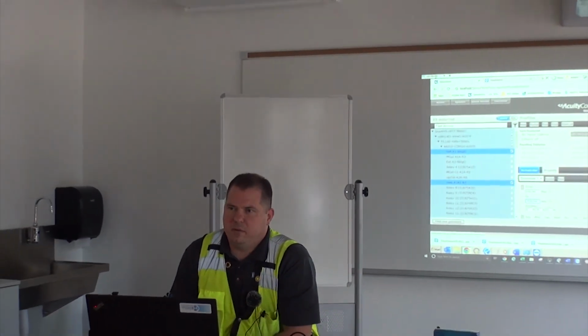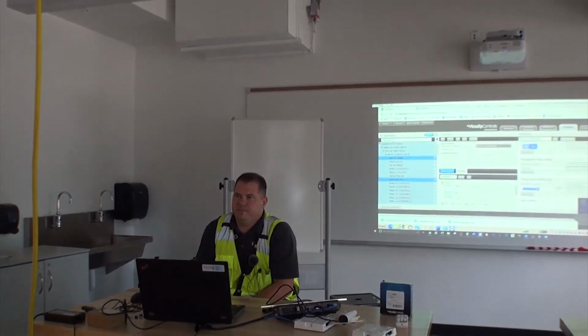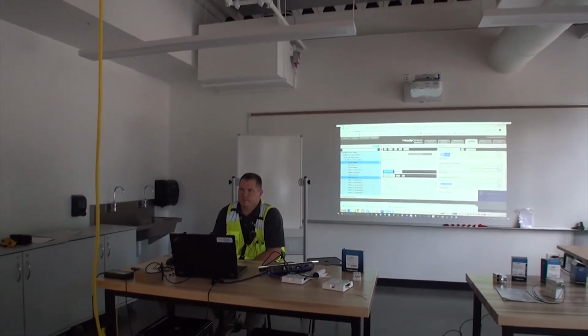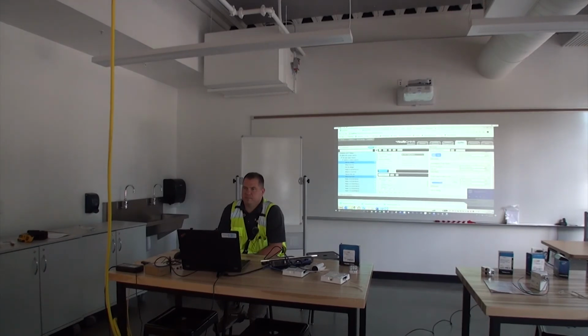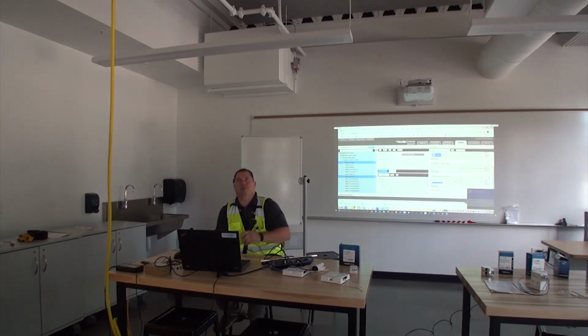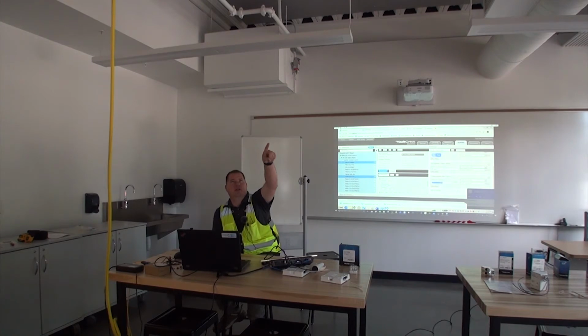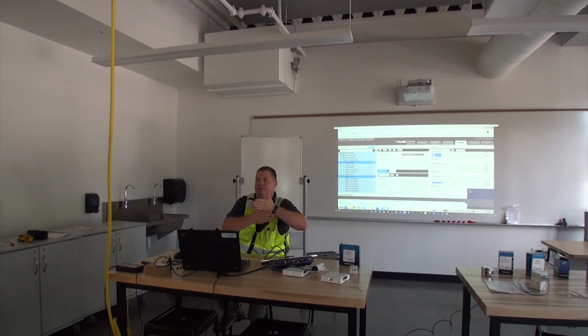As far as troubleshooting goes, I noticed it says to keep a 90-degree angle across power path lines and stuff when someone comes in to run power, since it's an inductive pump and not shielded. That all depends on how the contractor installed it, and I'm not 100% sure. If you have conduit, you're shielded because you're grounded. If you're freelining it, that 90-degree angle is much more important. So you can follow conduit as long as your bonding is good, you should be fine.